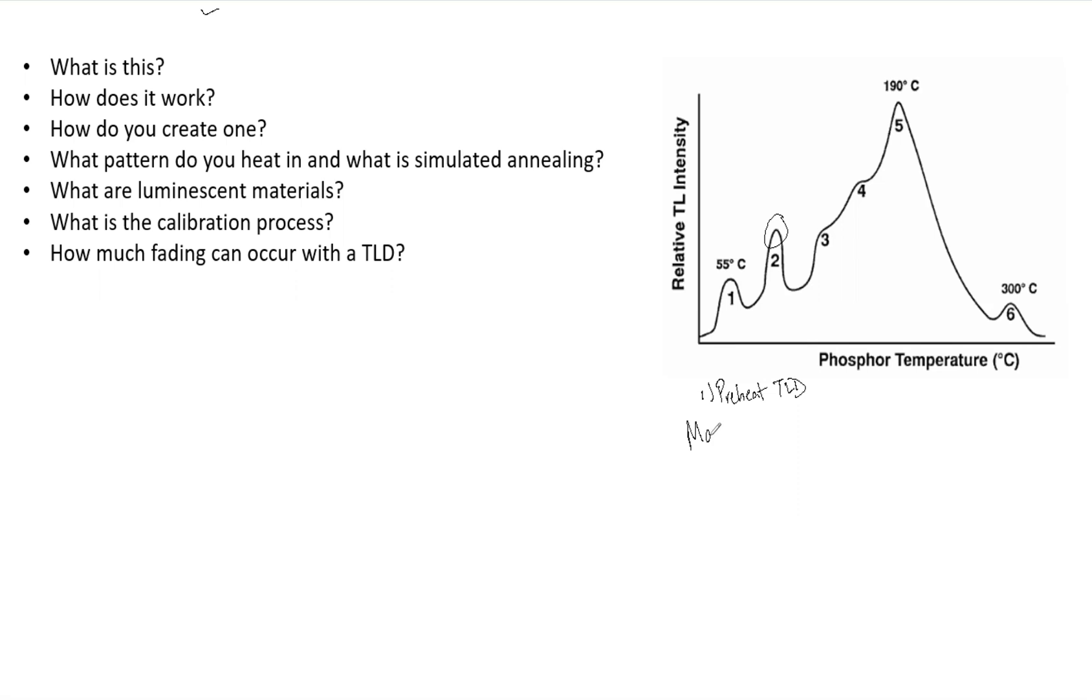One important thing is the maximum thermoluminescence for lithium fluoride, which is the most common TLD that we use in clinic, is approximately 180 to 260 degrees Celsius. Right here we see 190 degrees Celsius, and that is peak thermoluminescence.